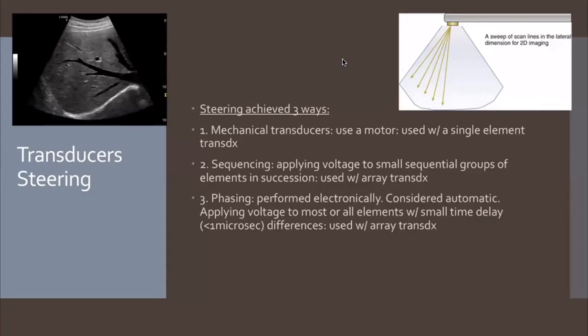The first way is with a motor, and this is called mechanical transducers. They have a little motor inside of them, and the motor rotates the PZT. This is done with a single element. There's only one PZT. So the motor turns this little PZT, and every time it turns the PZT, the PZT sends out a pulse. It's kind of like those sprinklers.